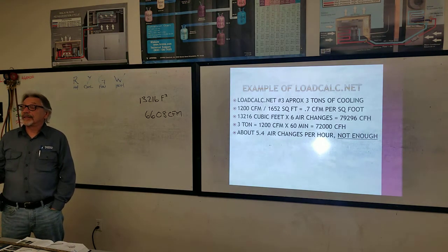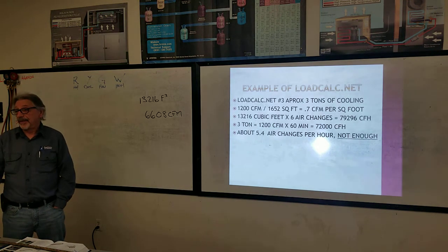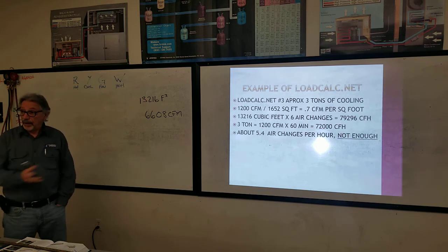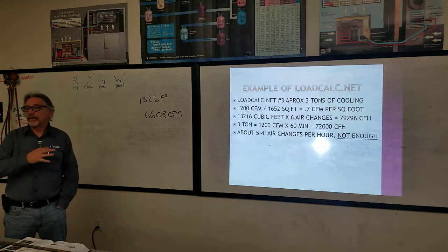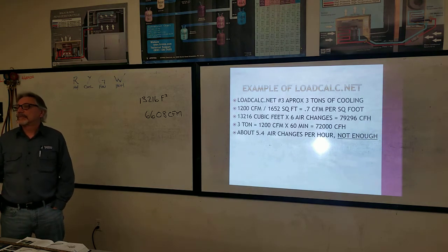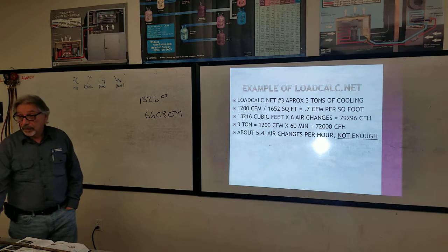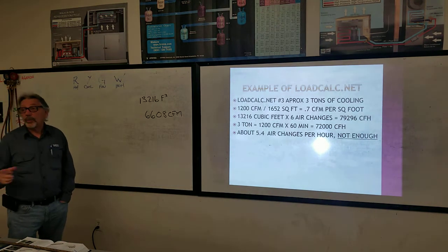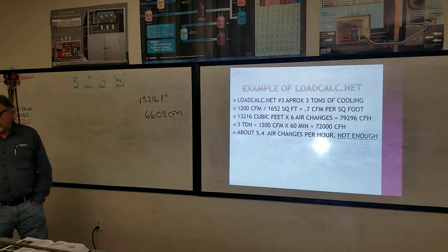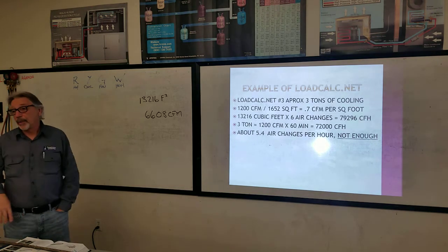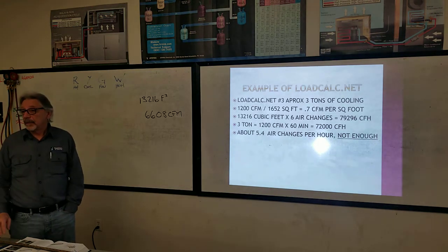It was about 75 degrees, and 105 outside, all evaporative cooling. Because we had enough air to move, the more air you move, the better off you're gonna be with water coolers. They can work really well, but the problem I've always seen is they just don't size them the right way.